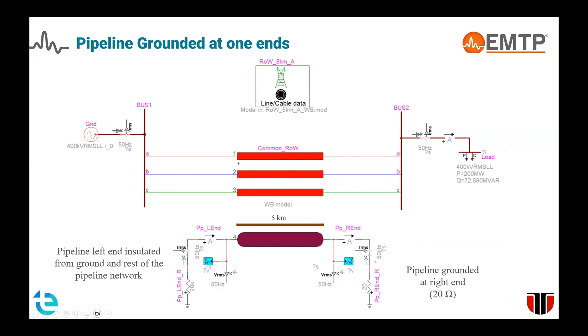If we model a first case where we have insulation at one end and connection to the ground of the pipeline at the other end, we can see that at the end which is insulated from the ground and from the rest of the pipeline system, there is an increase of the induced potential. At the end which is grounded, the induced voltage decreases. At the level of the currents that flow from the pipeline to the ground, this is reversed.